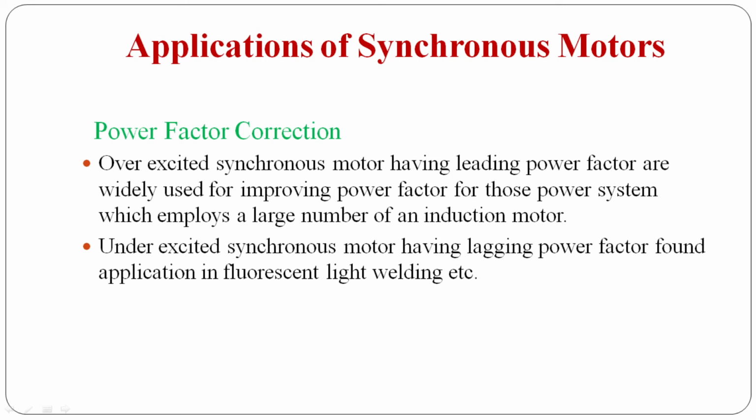First one, let us see power factor correction. Over-excited synchronous motors having leading power factor are widely used for improving power factor in power systems which employ a large number of induction motors. So over-excited synchronous motors having leading power factor will be used for improving power factor for those power systems which employ a large number of induction motors. Under-excited synchronous motors having lagging power factor find application in fluorescent lighting, welding, etc.